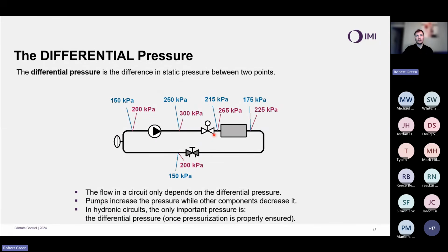I then have a control valve, and that is removing now 35 kilopascals. 250 to 215. I have a terminal that is now removing 40 kilopascals. 215 to 175. And finally, the job of the balancing valve is to remove that last difference of 25 kilopascals to go from 175 back to 150, because we must start again at the same static pressure as we started. We cannot have a difference in pressure between, in this example, there's no pipework resistance to simplify it. We must have the same starting point here.